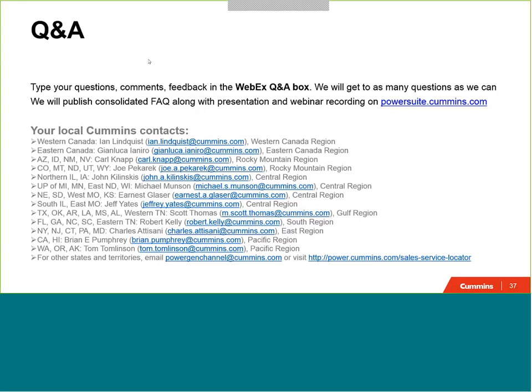One test that I'll pick on, for example: a manufacturer offering a product intended only for a standby market may conduct fewer hours of endurance or durability testing, whereas if it's going to a prime market, it may be tested longer in order to ensure that it meets market expectations. That's what the manufacturer may be doing themselves, but as I stated before, every manufacturer is going to be doing something differently based on their expectations. If you have different expectations for a prime generator set versus a standby generator set, clearly define what those are in order to ensure the generator manufacturers are meeting your expectations.